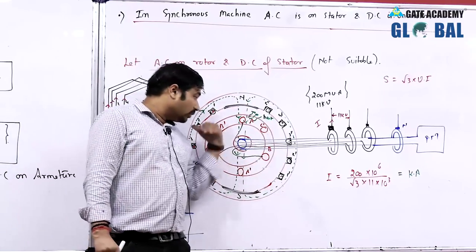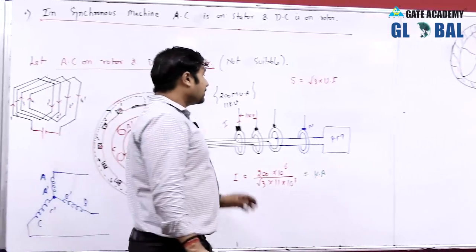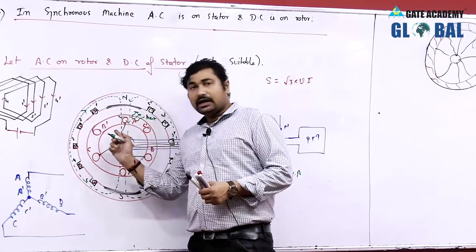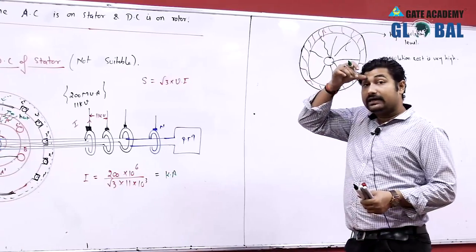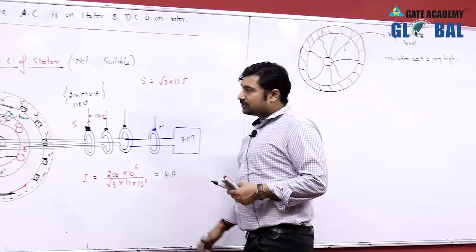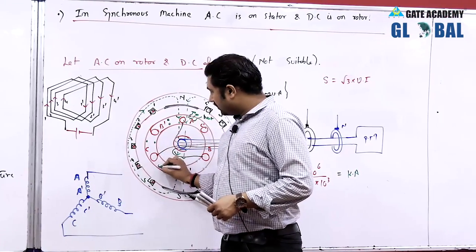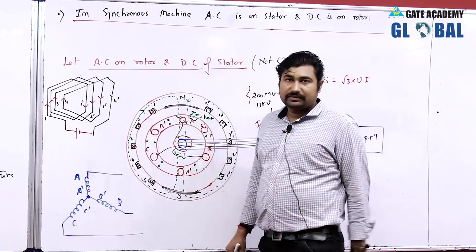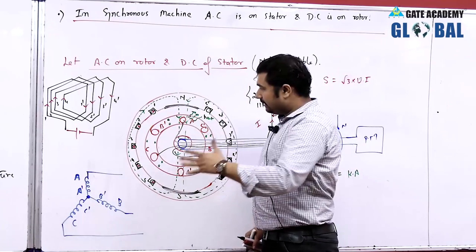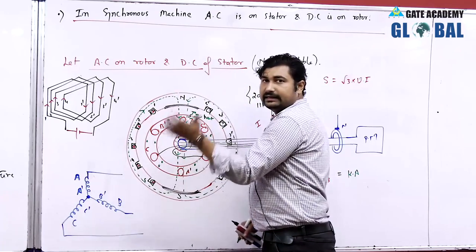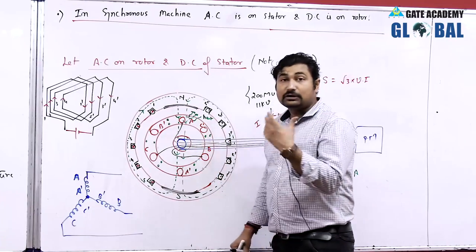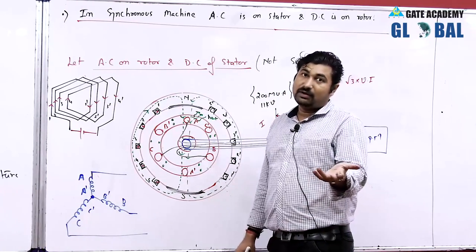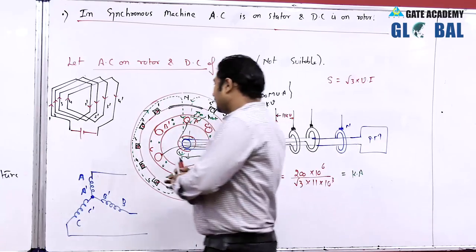We cannot fill oil between the stator and rotor as that makes rotation very difficult. Effective cooling requires a coolant — the best available being hydrogen coolant through cooling ducts. But if cooling ducts are provided on the rotor, it becomes very difficult to blow hydrogen gas through them as the rotor is rotary in nature. Also, we cannot allow hydrogen gas to leak in the presence of electric current and heat because hydrogen is explosive. So effective cooling is not possible if AC is on the rotor.